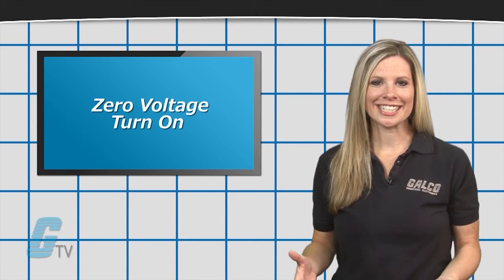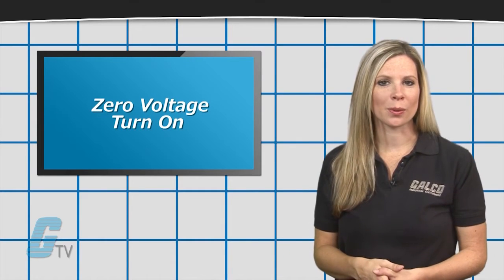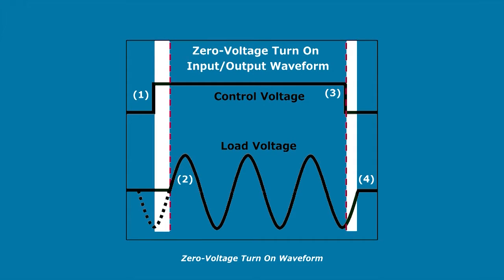Zero Voltage Turn On is ideal for resistive loads. It is a control circuit which allows an output to switch on the load current when the AC voltage is near the zero voltage point. Usually a control signal is supplied.